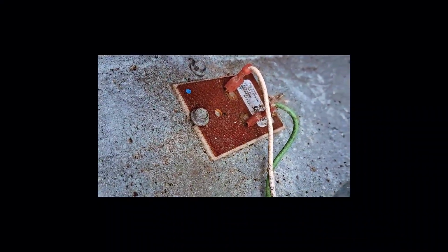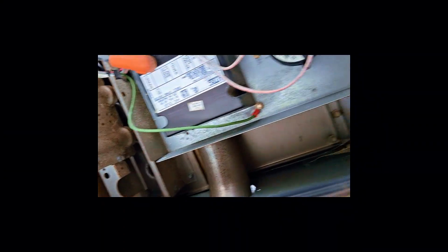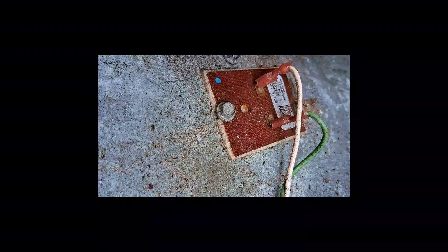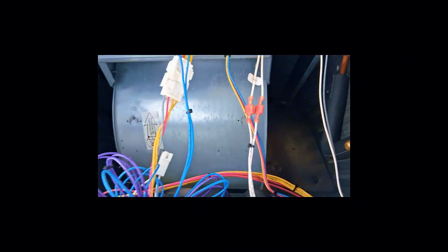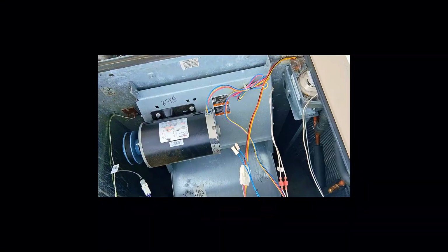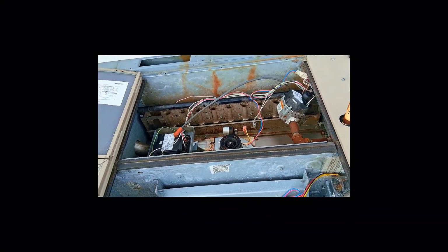I think there's a blower limit switch right here. I think you have to pull that up to see, because that's reading inside the heat exchanger section. So you have to undo that and pull it out to look at it, see if it needs to be replaced, see if it's getting too hot, or if it's in bad shape. But everything else on this thing is okay. Once we do that, I think we'll get the system back online. Alright guys.